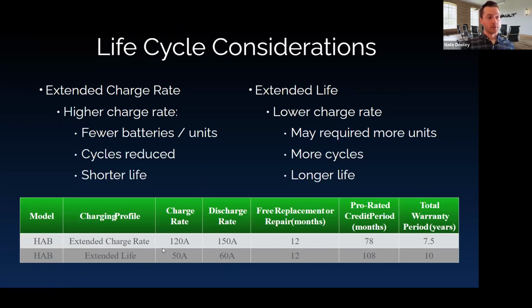The simple solution would be to add a second HAB, or just limit your maximum output on the inverter so that your discharge rate stays under 150 amps. So conceivably 14 HABs in parallel would give you 150 amps times 14, and you'd be hard pressed to find a single inverter on the market that exceeds that. But obviously a stacked system of inverters can amount to some pretty high discharge currents. That's the rough math I'd follow to figure out how your inverter size compares to the quantity of batteries required.